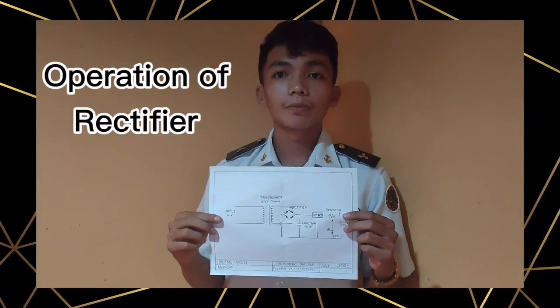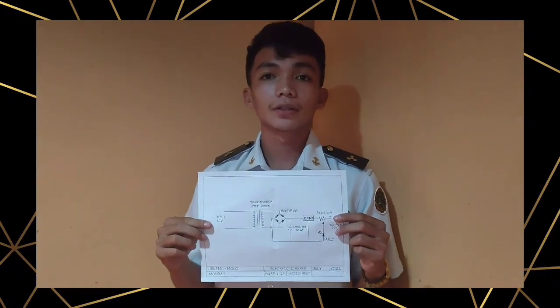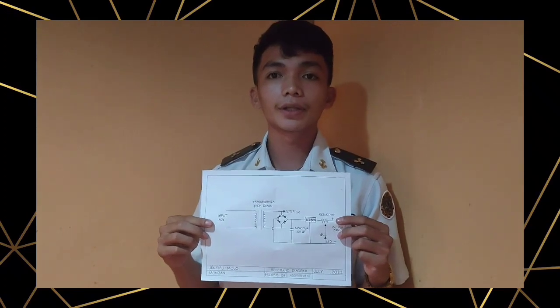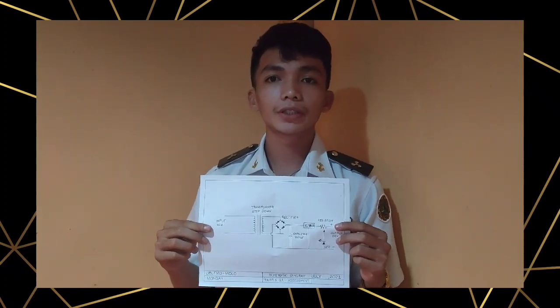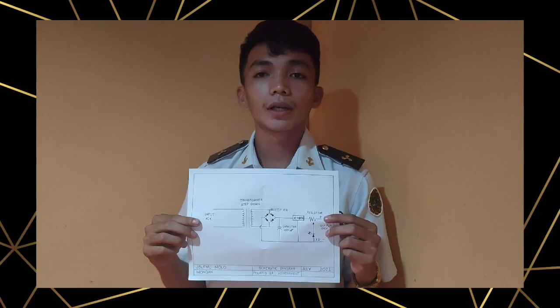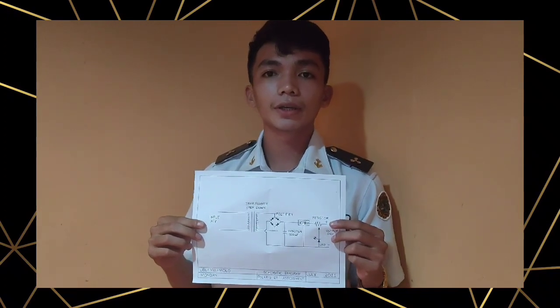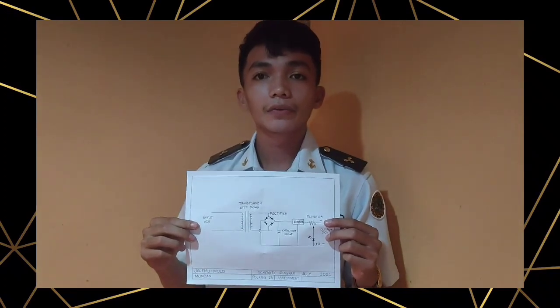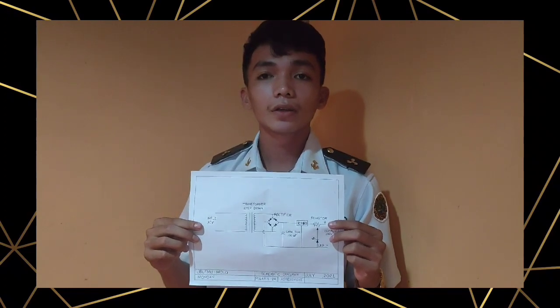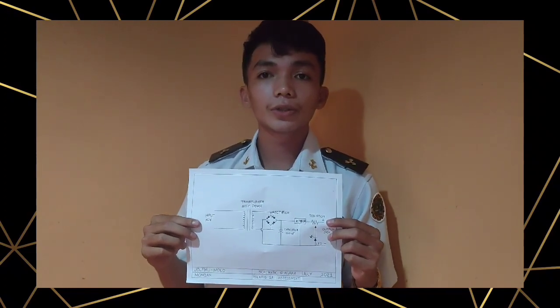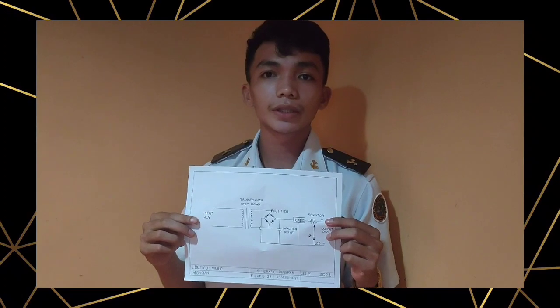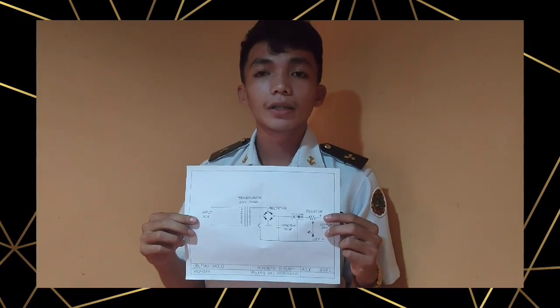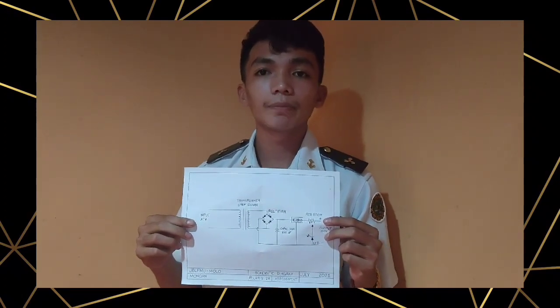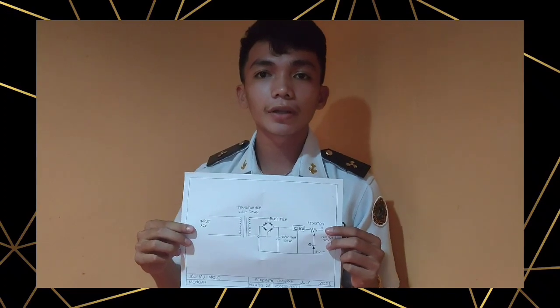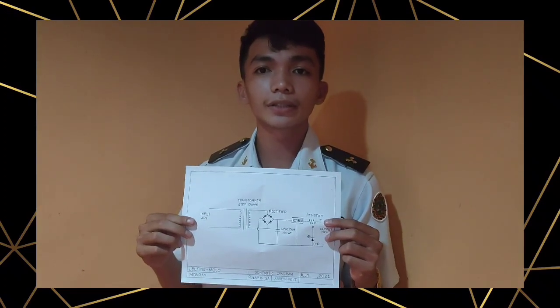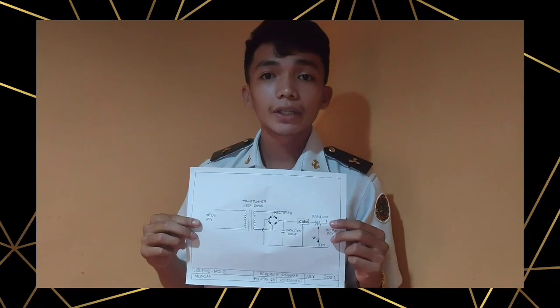There are three major components in a rectifier: the transformer, stack, and cabinet. The purpose of the transformer is to safely separate the incoming AC voltage on the primary side from the secondary side, which is adjusted to control the output voltage of the rectifier. Typically, these adjustments are made with tap bars connected to the secondary side windings at intervals, offering several setting options.